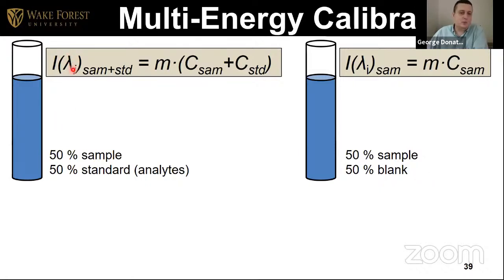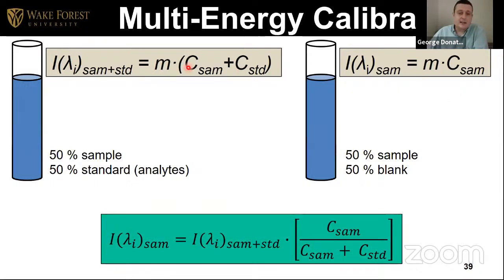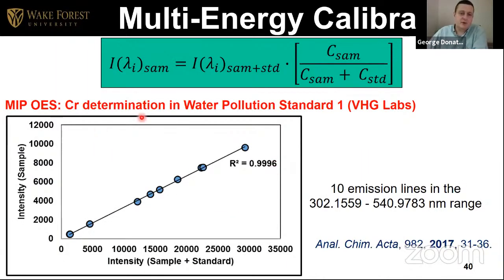If we look at the signal at a certain wavelength, the instrument response is a proportionality constant times the concentration of the analyte, which comes from the standard and the sample. And in this solution, it comes only from the sample. Because this proportionality constant is the sensitivity of that wavelength, you can equalize those 2 equations, and it looks like this. Then what we do, if we plot, for example, in the y-axis the intensity coming from the sample, and the intensity coming from the first solution, sample plus standard, if we plot those two, you get a very linear curve, and each of these points represents a different wavelength. So you have the intensity for each of the solutions at one wavelength, another wavelength, and so forth. In this example, we have 10 emission lines of chromium for this measurement.